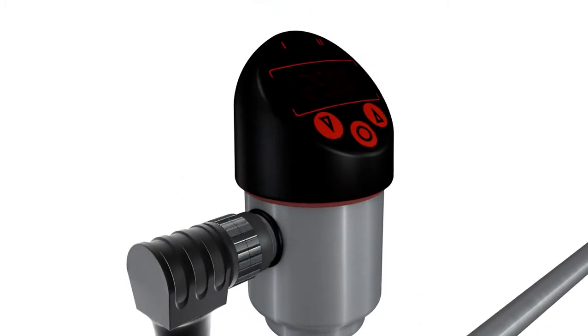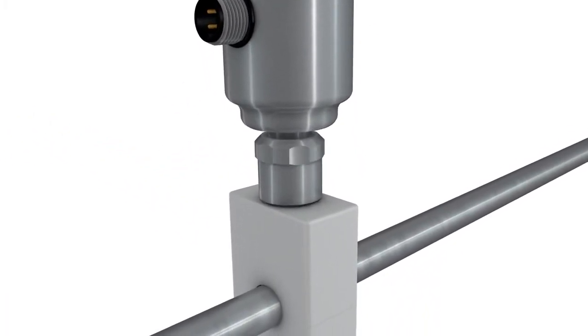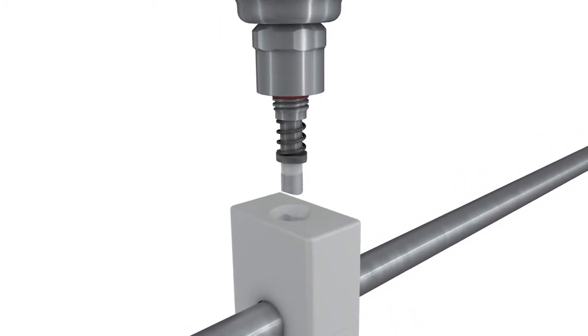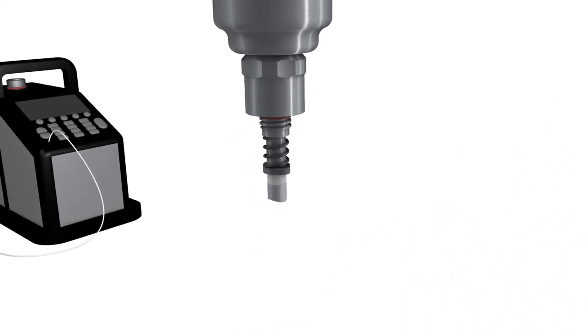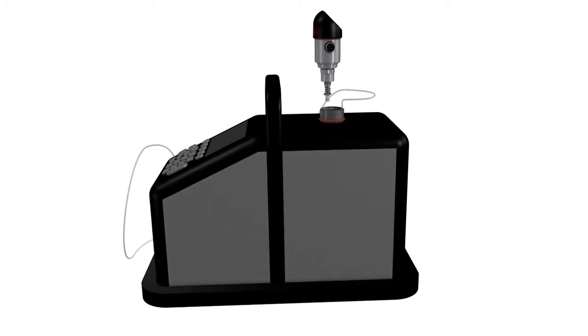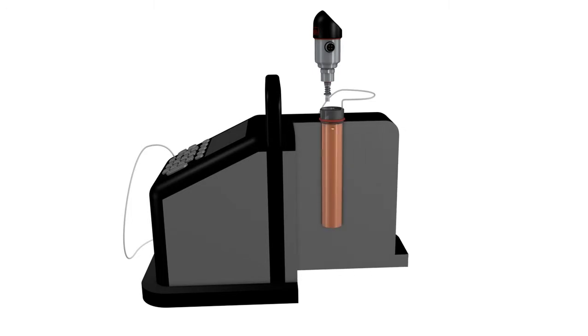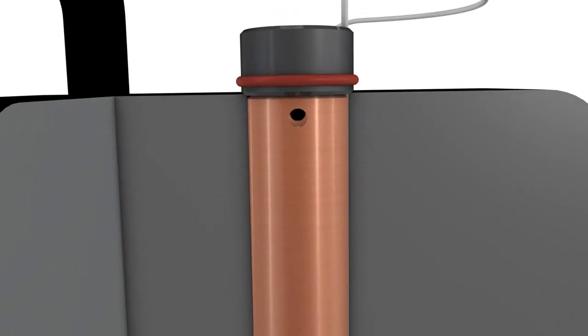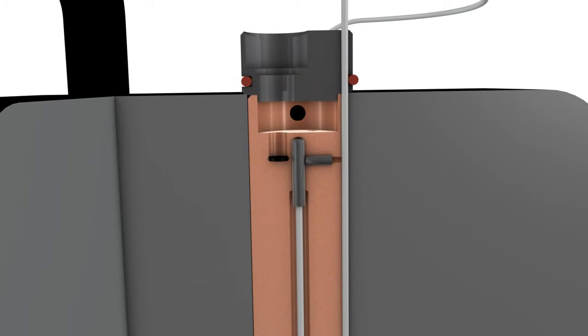Now we want to show you how easy it is to recalibrate the LABOM Clamp-On sensor. You simply unscrew the temperature sensor and remove it from the clamp block. There is no disruption to the process. The clamping block that defines the measuring spot remains on the pipe. We recommend the use of a dry calibrator equipped with a customized insert to hold the sensor being calibrated to keep the whole process very quick. You can, of course, use a conventional calibrator if you wish. See your calibration guidelines for Clamp-On model series for details.